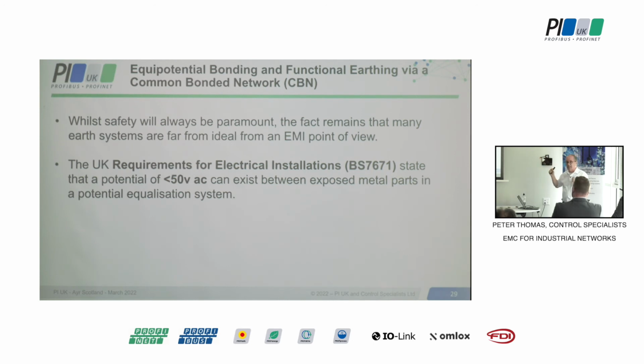So what we're saying is, if you've got two panels, a large distance between them, and you're running Profibus or Profinet cable, and you follow the recommendation of grounding the shield at both ends, there is a possibility that you might be putting 50 volts across that shield. So now our shield becomes an equipotential bonding conductor, which it wasn't designed to be. So when we say ground at both ends, there's an unspoken assumption that this is a bonding infrastructure designed for EMC as well as safety, which not all of them are.